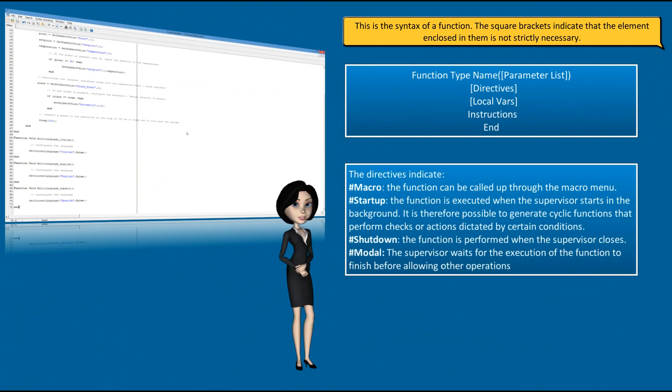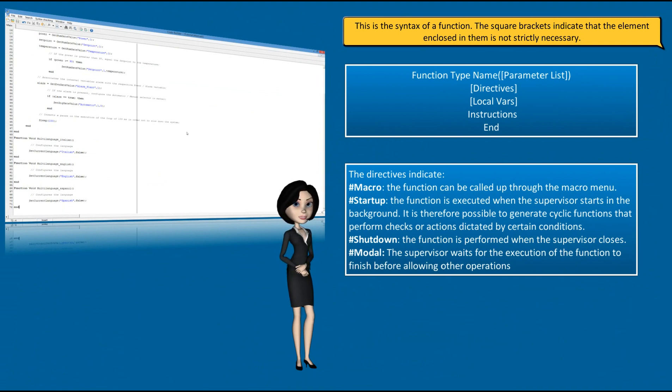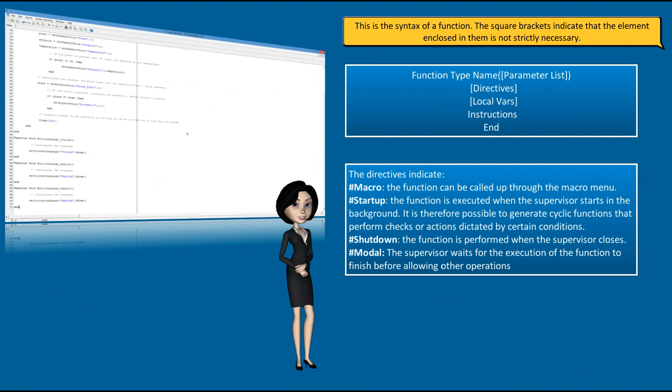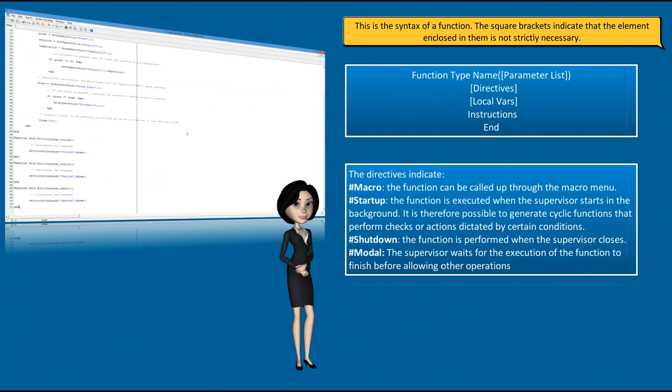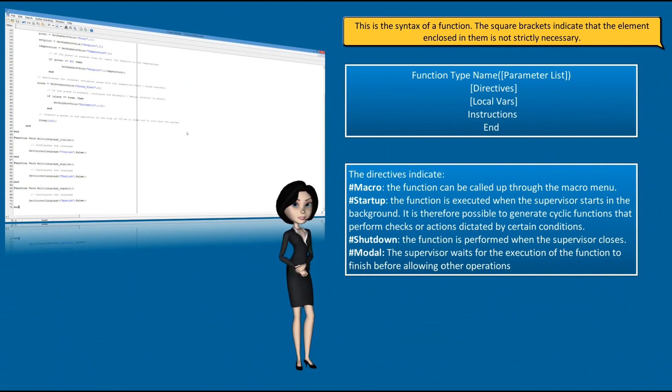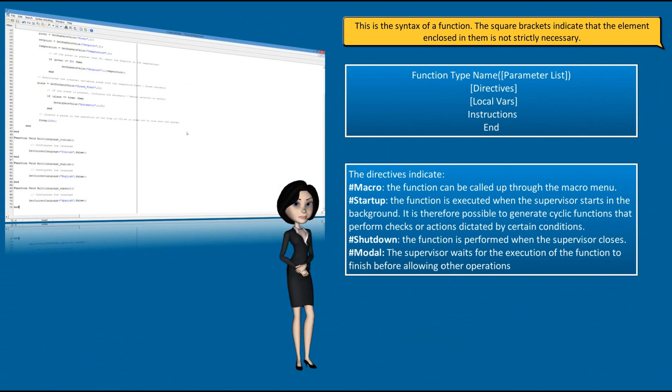The directives indicate: Macro, the function can be called up through the macro menu. Startup, the function is executed when the supervisor starts in the background. It is therefore possible to generate cyclic functions that perform checks or actions dictated by certain conditions. Shutdown, the function is performed when the supervisor closes. Modal, the supervisor waits for the execution of the function to finish before allowing other operations.